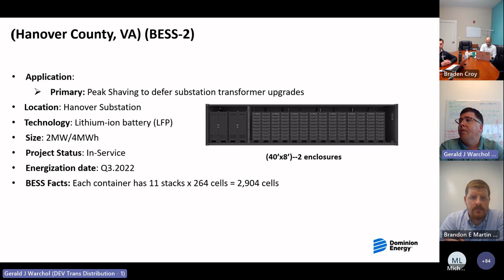Going into the specifics of the site construction, we have subtle differences, and these were all intentional to test and understand what our substation department liked better for construction. You saw a concrete pad for the enclosures at correctional, and we have pier foundations here in this middle photo for Hanover. But one major difference is with the enclosures down along the bottom - you come up, hang a right, and the inverters are outside of the enclosures.